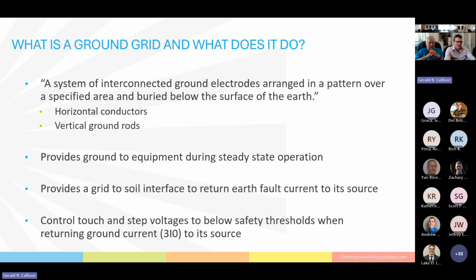During fault operations, where you have a ground fault, the ground grid provides an interface between the grounding system and the soil that current enters and then travels through the soil back to its source, remote earth. And basically, a ground grid ensures that when this current is entering the grid to soil interface during faulted conditions, touch voltages and step voltages throughout the station are maintained below safe thresholds. We'll talk a little bit about what touch and step voltages are in a few slides.